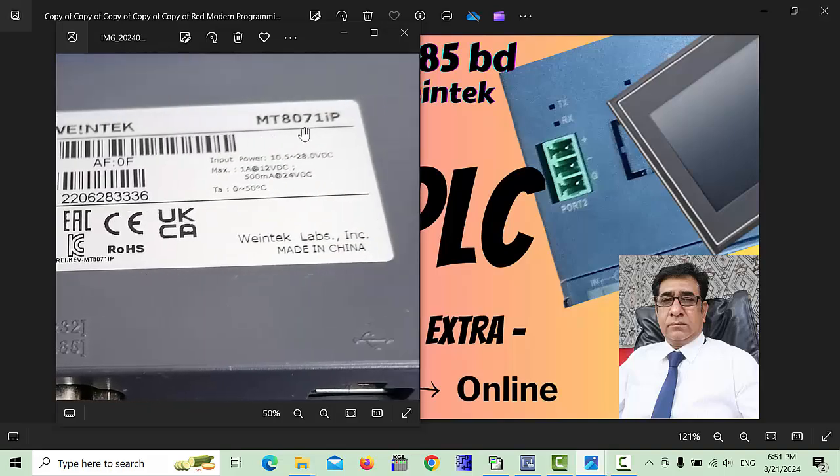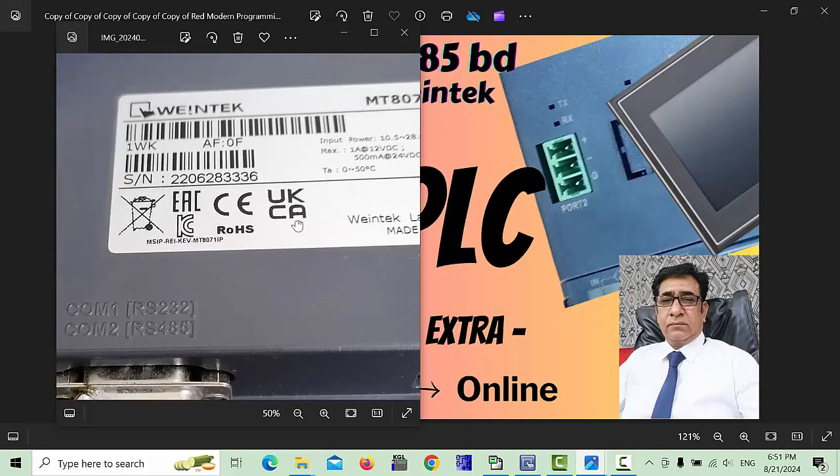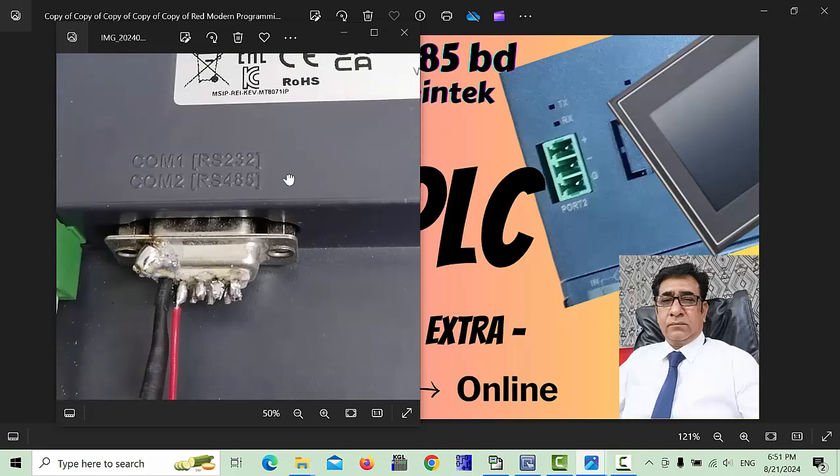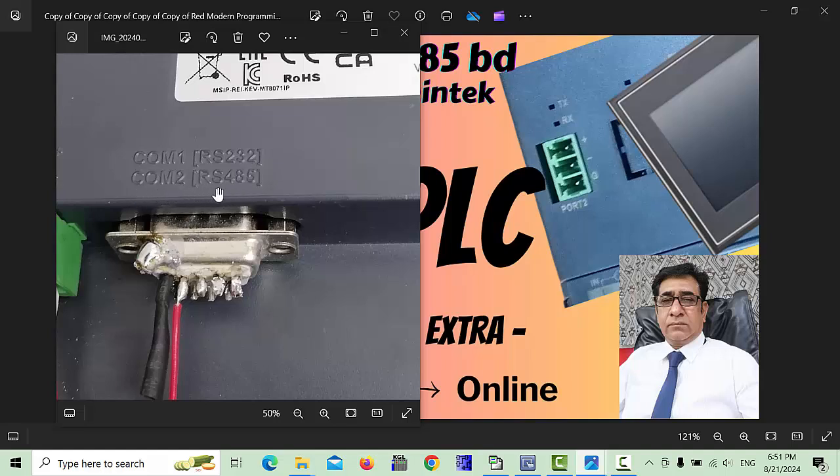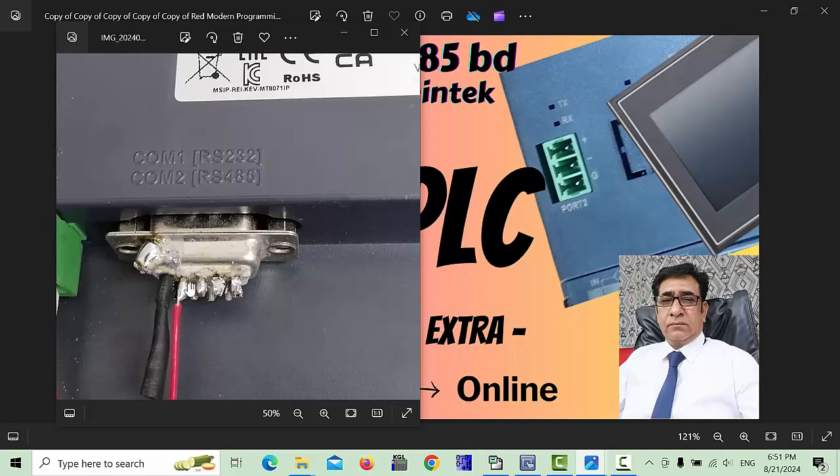This model is MT8071IP, and this is the COM1 port RS232 you can use, and COM2 port you can use RS485. This first number pin and second number pin - first pin is minus voltage and second pin is the plus voltage to the PLC board.